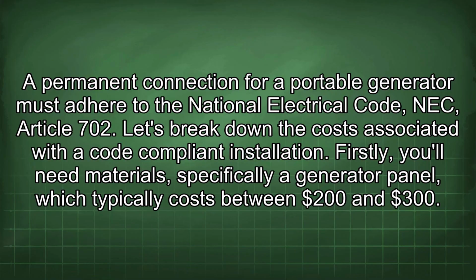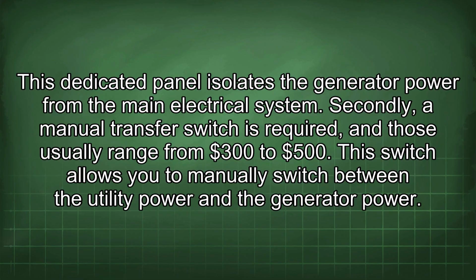A permanent connection for a portable generator must adhere to the National Electrical Code, NEC, Article 702. Let's break down the costs associated with a code-compliant installation. Firstly, you'll need materials, specifically a generator panel, which typically costs between $200 and $300. This dedicated panel isolates the generator power from the main electrical system.